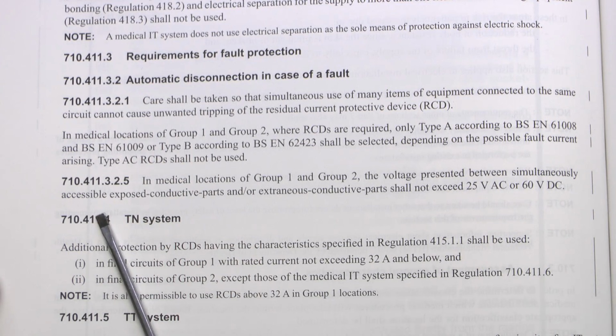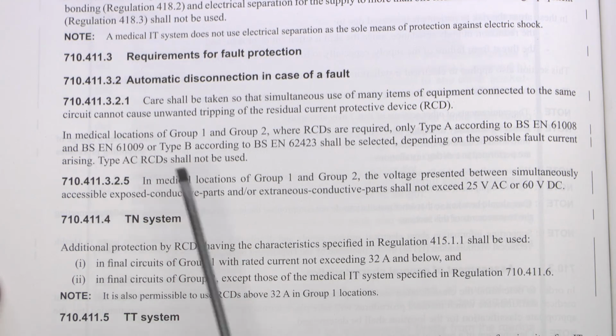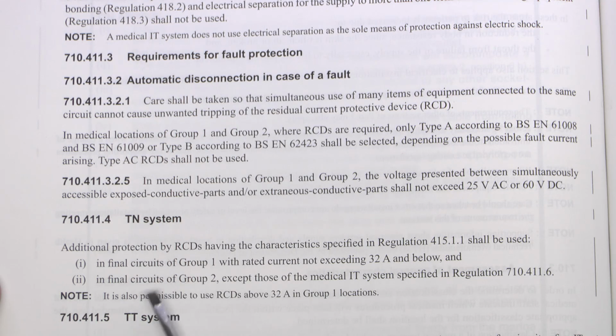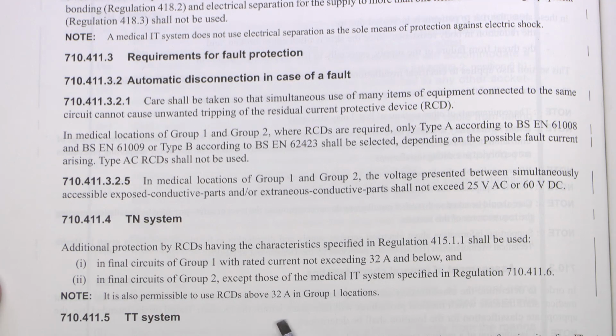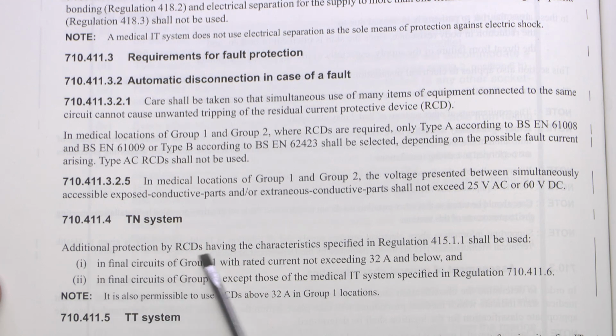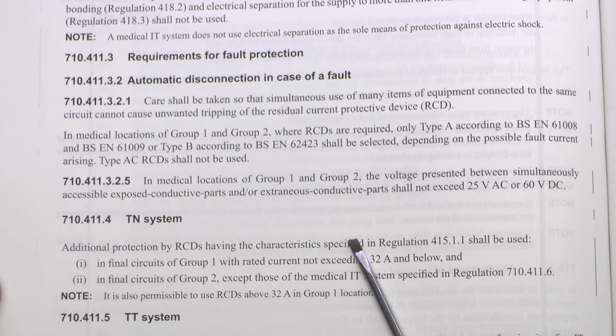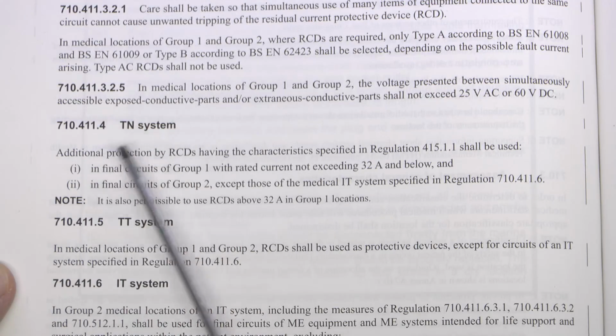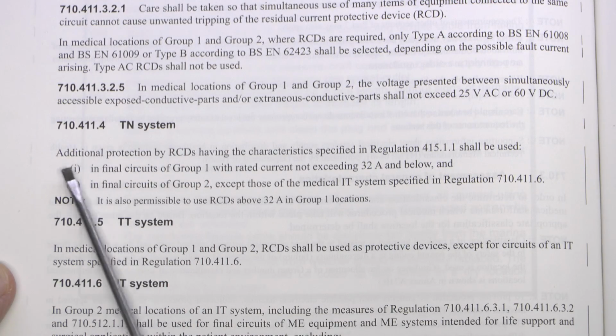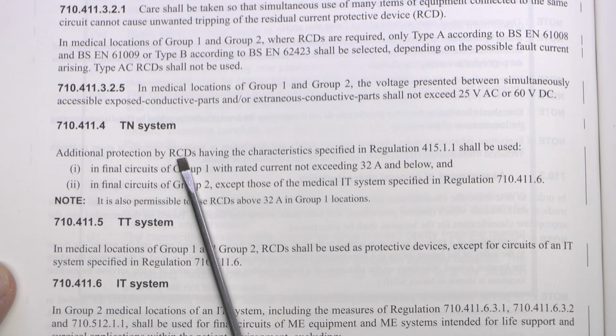And another one that's been deleted immediately after this is 710.411.3.3, and that was about additional protection with an RCD. However, though that's been deleted, the basic text has been incorporated into the following parts here, so it does actually still exist in there, as it says here, the additional protection by RCD, so it's been slightly expanded and basically renumbered and moved down.